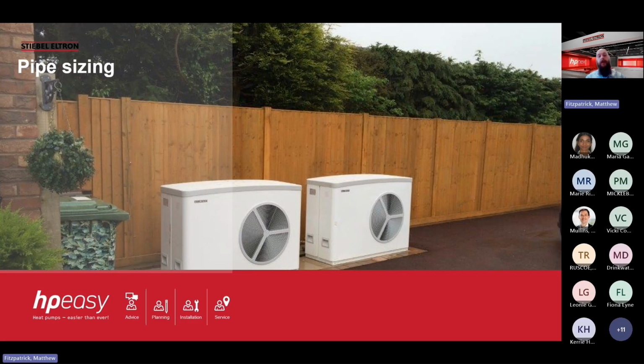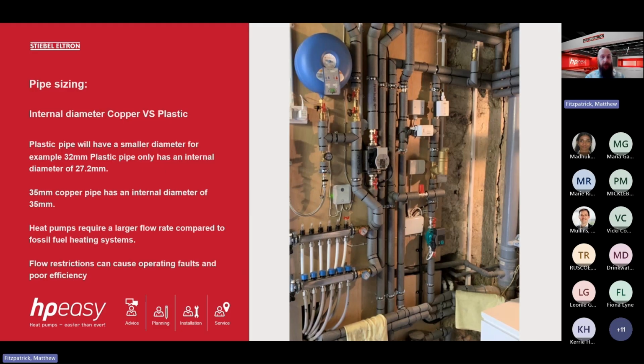So pipe sizing. I will just add, this is quite an in-depth topic, so I'm just touching on a few key points, things that you can use and may be useful moving forwards. There may be some more information coming out about tips and tricks on pipe sizing and pump sizing. So the first key point I always make is the internal bore. There is a big difference between plastic pipe and copper pipe. So the internal bore of plastic pipe is normally smaller than the diameter it's advertised as. So if we look at 32 mil plastic pipe, that is the external diameter. The internal diameter is 27.2 millimeters, so almost 5 millimeters smaller.